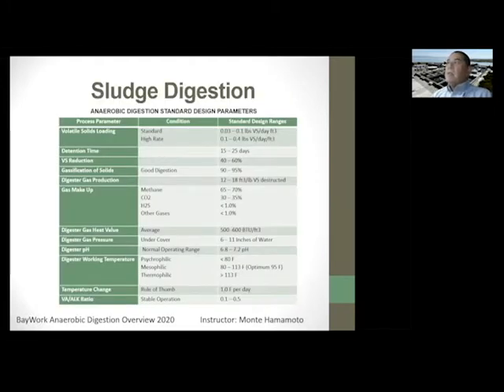One of the things that's very important: every treatment plant has what we call design parameters. It's how the engineers designed the plant to work. So we talk about volatile solids loading on your digester. That's basically the food that you're going to feed it. It talks about the ranges of how many pounds of volatile solids you could feed per cubic feet of digester space that you have, or volume.